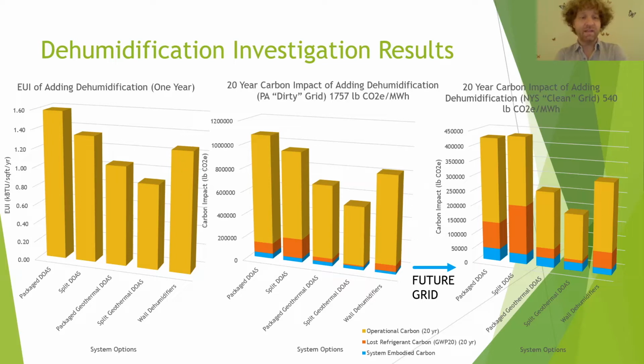On the left is the energy use intensity of adding dehumidification for one year. Packaged dedicated outside air system: decent. The split system is better—about 15% better in this climate, and most of that energy difference was in low temperature performance, not cooling at all. It's all in the defrost cycles, because VRF can operate at really low temperatures, whereas the packaged dedicated outside air systems can't really do that.